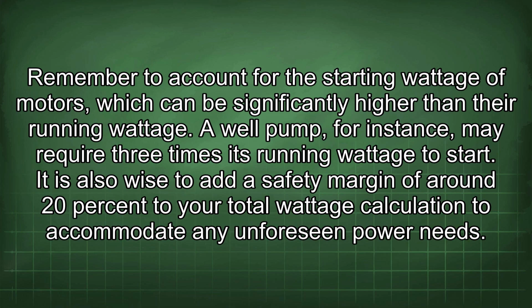A well pump, for instance, may require 3 times its running wattage to start. It is also wise to add a safety margin of around 20% to your total wattage calculation to accommodate any unforeseen power needs.